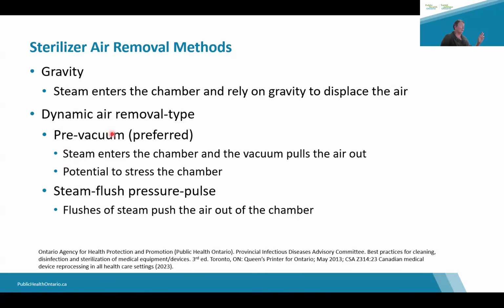And the next 2, the pre-vacuum and the steam flush pressure pulse, are both called dynamic air removal. The pre-vacuum is the preferred type of autoclave because here the sterilizer actually pulls the air out of the chamber of the autoclave, allowing the steam to come in. But when it does that, it drops the pressure in the chamber below atmospheric pressure. And if there's a leak in the chamber, then air can re-enter the chamber. And that is not good because then this air is going to take up space that should be occupied by steam. And that's going to make it more difficult for the steam to reach all the surfaces of the items to be sterilized. So this is why you have to do a Bowie-Dick test every day to ensure that the vacuum system is adequately removing the air out of your pre-vacuum sterilizer.